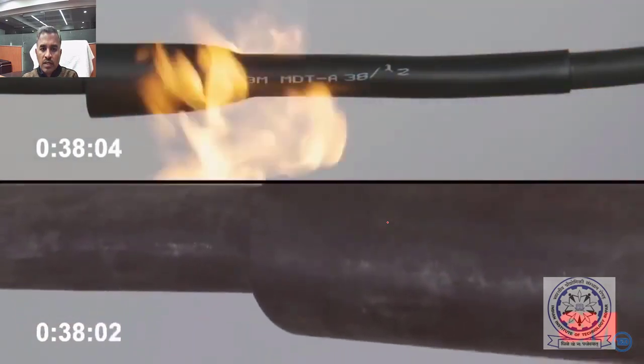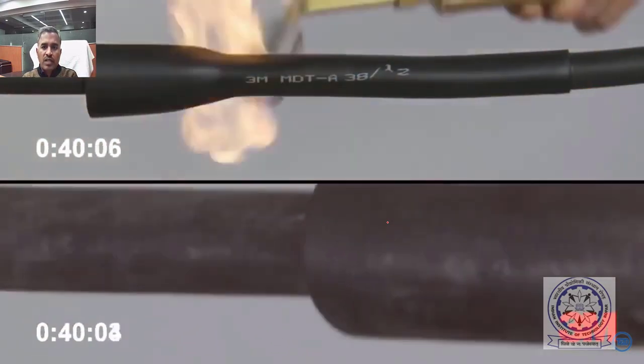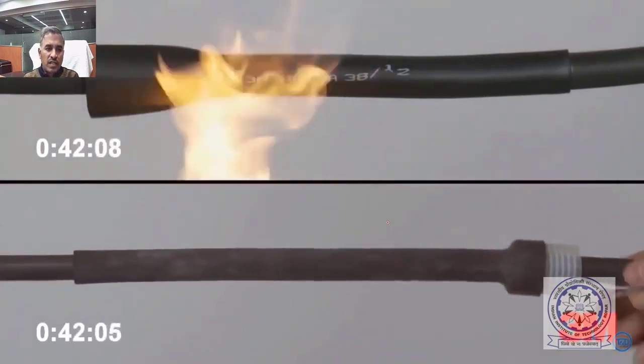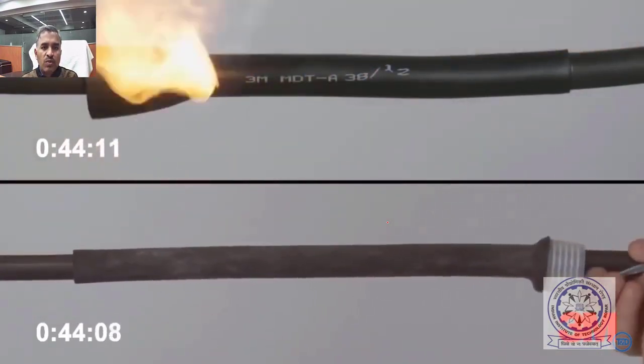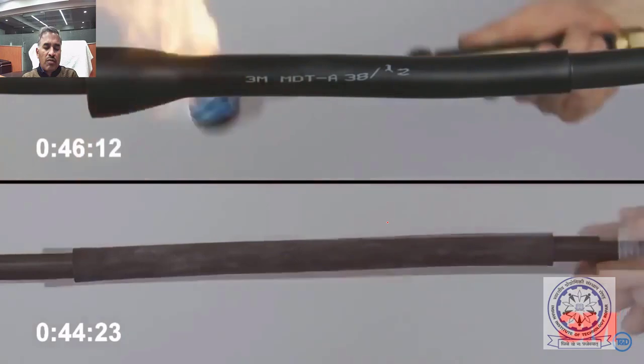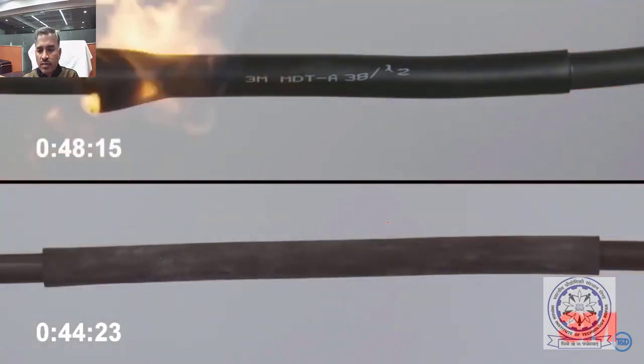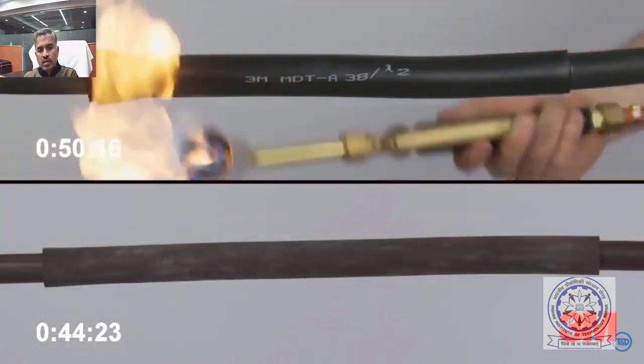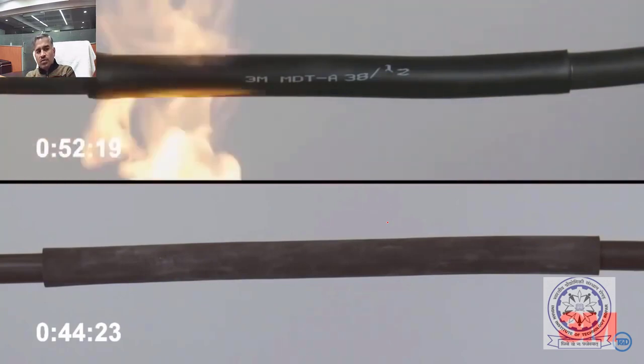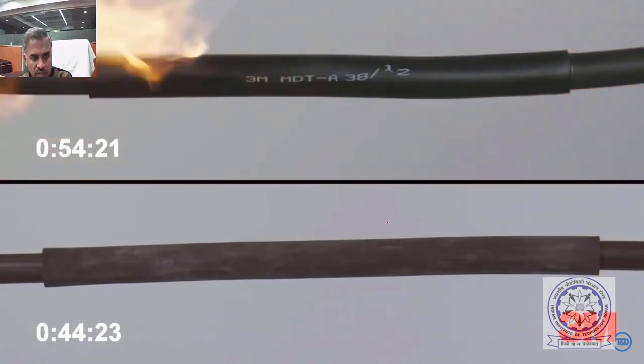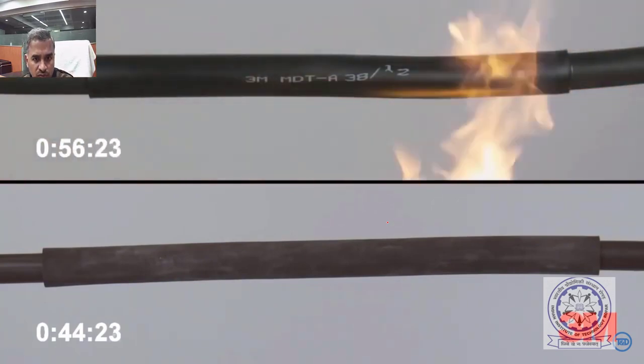In case of heat shrink, you should start from the middle and finish one end and then the other end in order not to have air inside. Cold shrink, simply it is elastic, so under different weather conditions also it will react to the situation, but it's not the case with heat shrink.